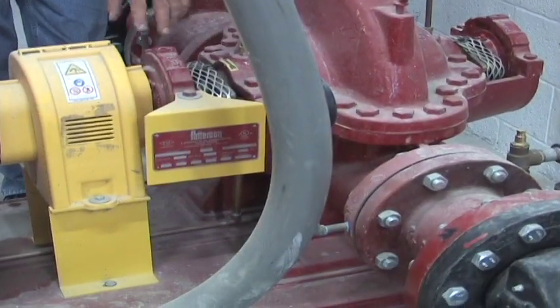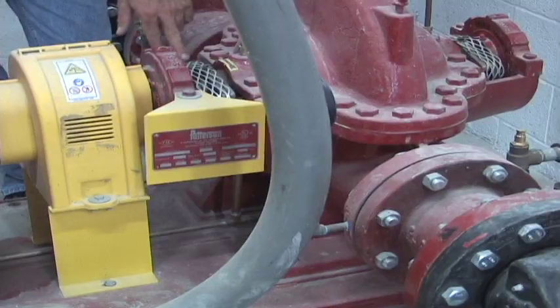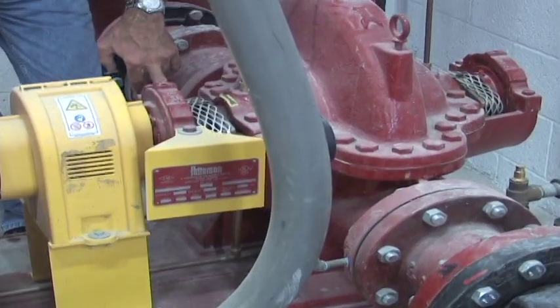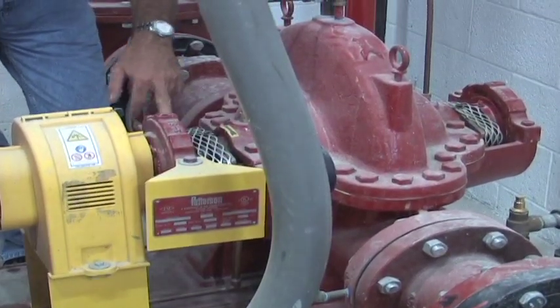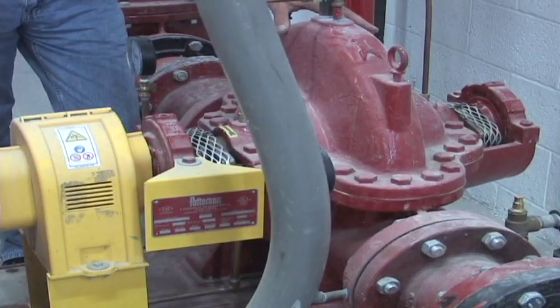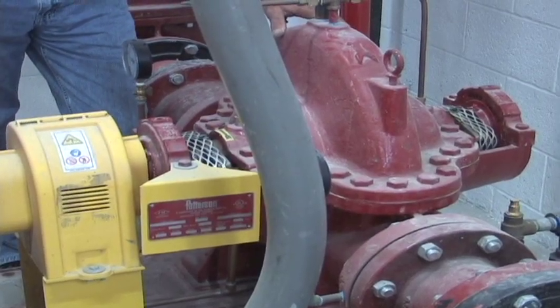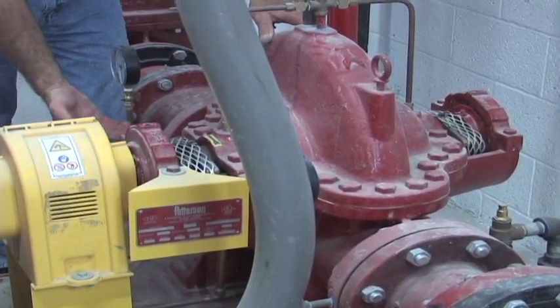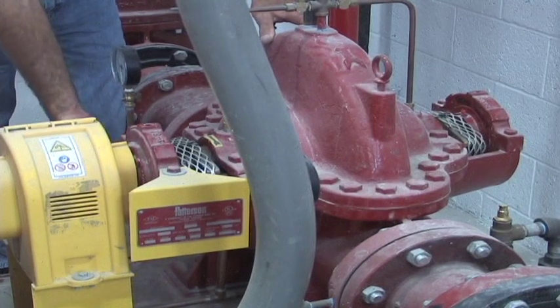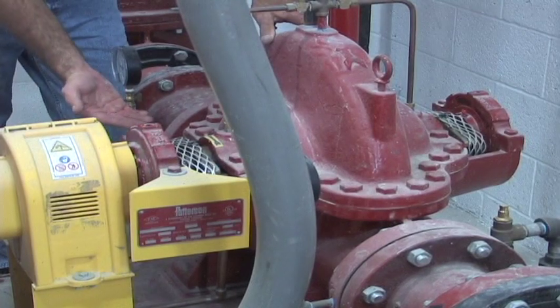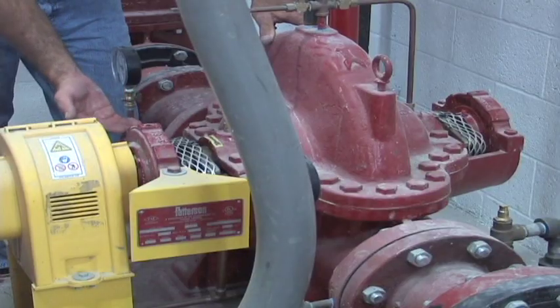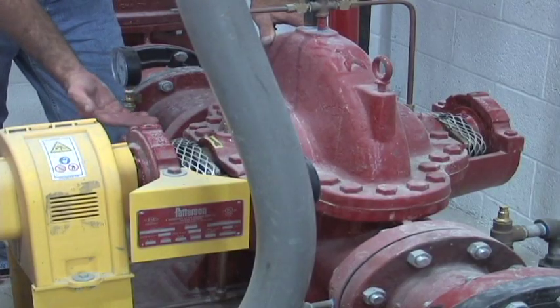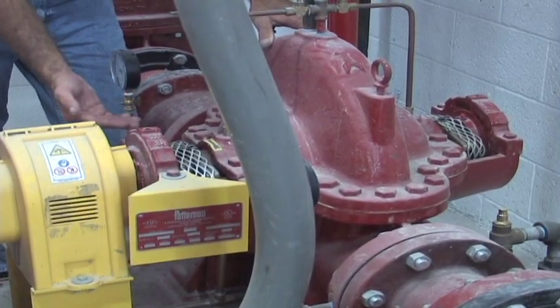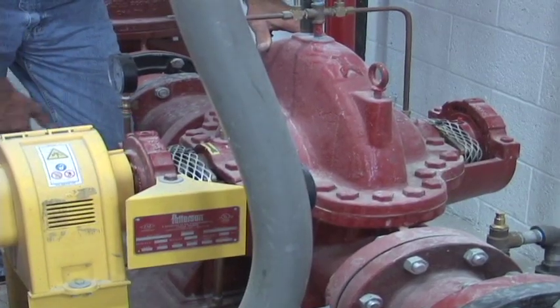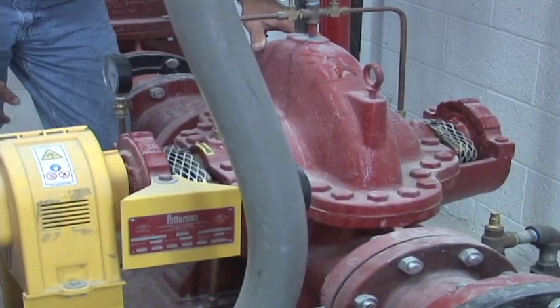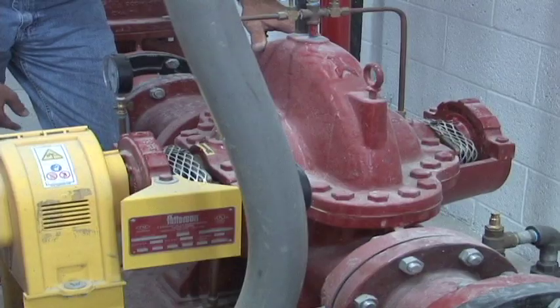after time builds all up, these drains will start to get clogged all up. Got to make sure that both the inboard and the outboard, the 1/2-inch hole that goes to the drain, stays clean. If for some reason they start to fill up with water, it's going to come up. The water's going to sit in the drip cups, and it's going to get into the bearing housings. As you start to get that water into the bearing housing, you're going to eat the grease up, and then you're going to start corrosion, start rust, and your bearing and your packing is going to get all torn up.